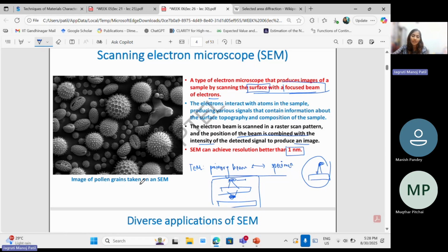In terms of specialized, our chamber in TEM is very limited. The size of the chambers is very limited, whereas in SEM we have enough working space. We almost have 10 to 15 centimeters of working space apart from our specimen where we can do other kinds of analysis, and we can insert multiple detectors at the same time. Whereas in TEM, we do not have that much space. It's only doing one particular operation at a time, that operation being the beam passing through your condenser lens, going to your objective lens, finally making an image for you.